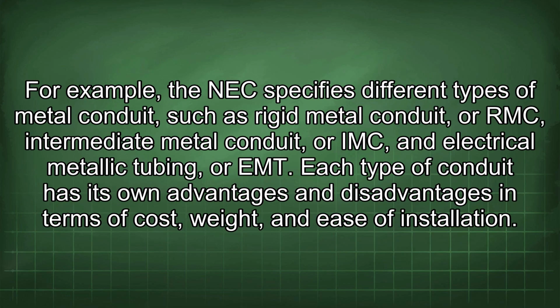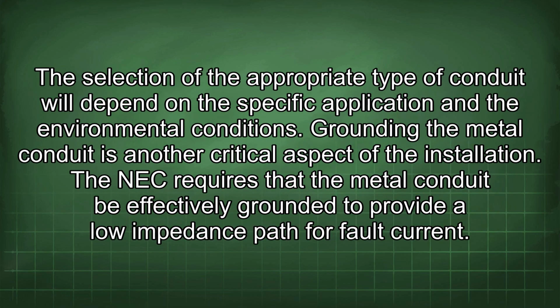For example, the NEC specifies different types of metal conduit such as rigid metal conduit, or RMC, intermediate metal conduit, or IMC, and electrical metallic tubing, or EMT. Each type of conduit has its own advantages and disadvantages in terms of cost, weight, and ease of installation. The selection of the appropriate type of conduit will depend on the specific application and the environmental conditions.